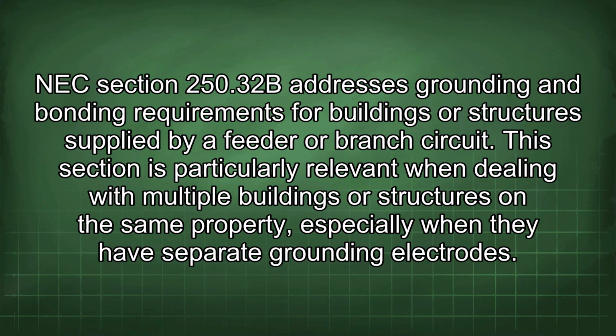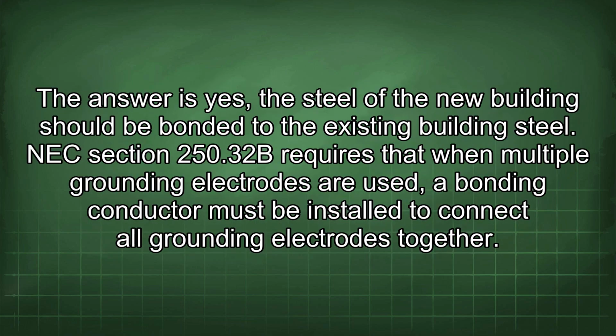NEC Section 250.32b addresses grounding and bonding requirements for buildings or structures supplied by a feeder or branch circuit. This section is particularly relevant when dealing with multiple buildings or structures on the same property, especially when they have separate grounding electrodes.